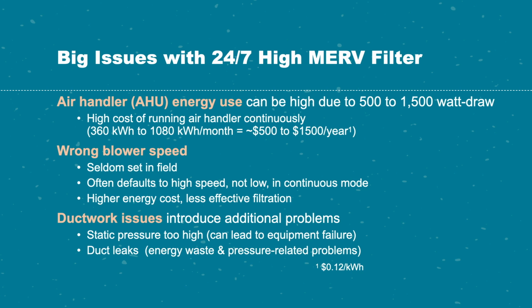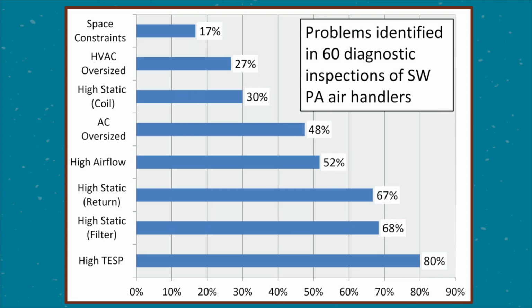And then the other issue is if you've got any duct problems, particularly if you've got ducts in an attic, a garage, a crawl space, you can have tremendous energy waste, pressure-related problems, humidity issues. So anything wrong with your duct system is only going to be worse if you run it 24/7. This is what we've seen, and this is just a plot. It hasn't been updated, but basically a huge number of systems with static too high, all of these.